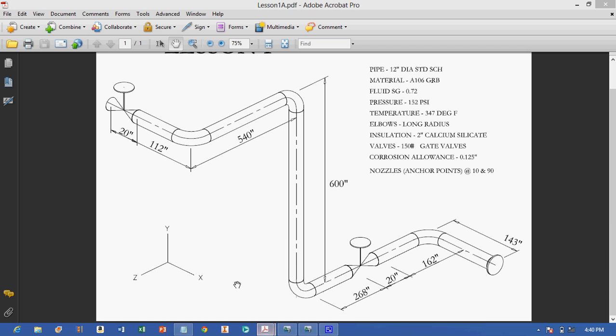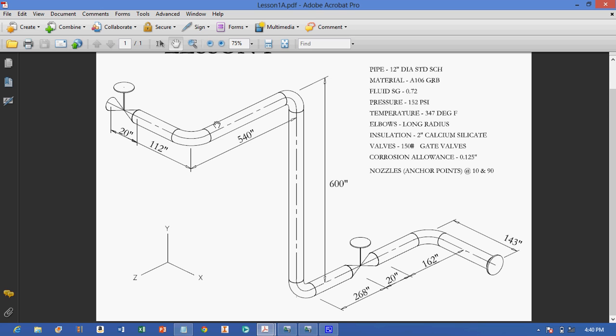In this example, we have a piping system with a valve and an elbow. There is a 12-inch pipe, standard wall — which is the same as schedule 40 — made of material A106 grade B. The fluid density comes from a specific gravity of 0.7, with a corrosion allowance of 0.125 inch, pressure of 152 PSI, and temperature of 347 degrees Fahrenheit.